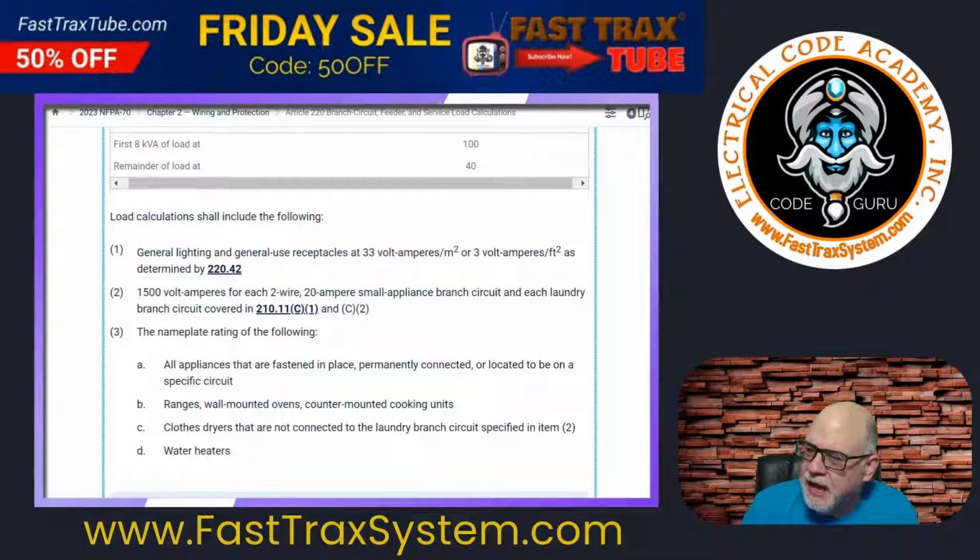All right. Next is your small appliance branch circuits. Again, 1,500 VA for each 2-wire 20 amp small appliance branch circuit. So if it's an existing dwelling, you're going to have to go and see how many small appliance branch circuits they actually have. Right, so that's important. And of course, laundry circuits as well.